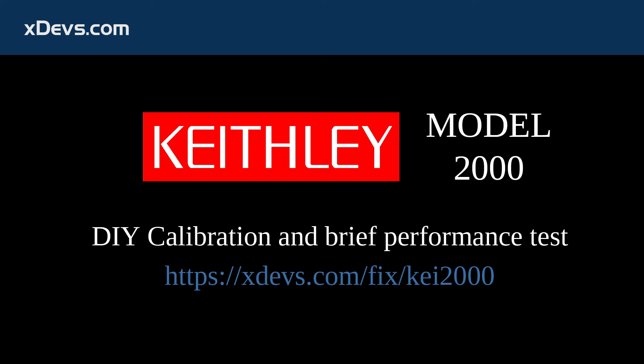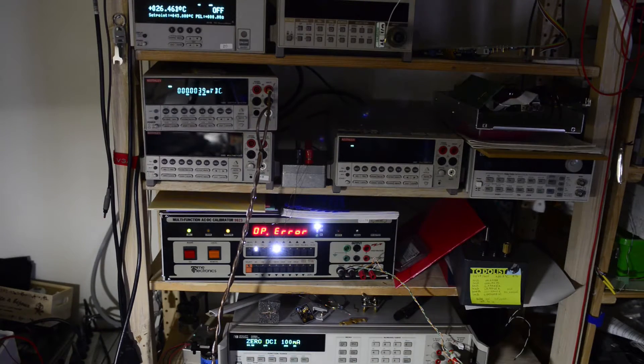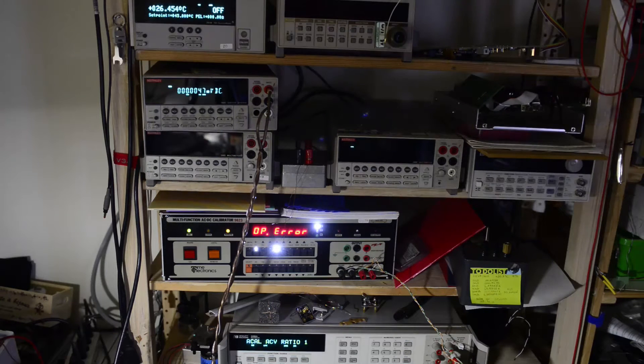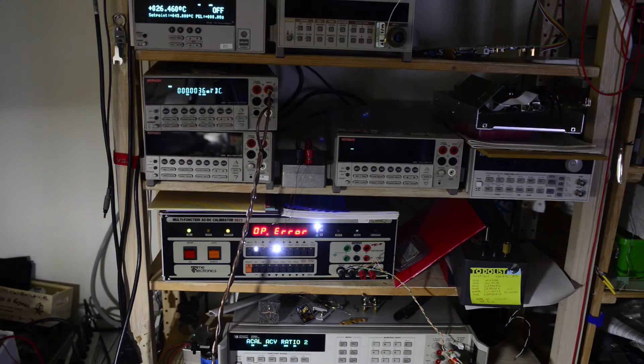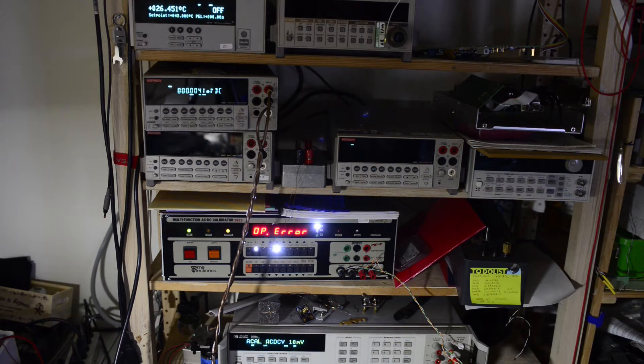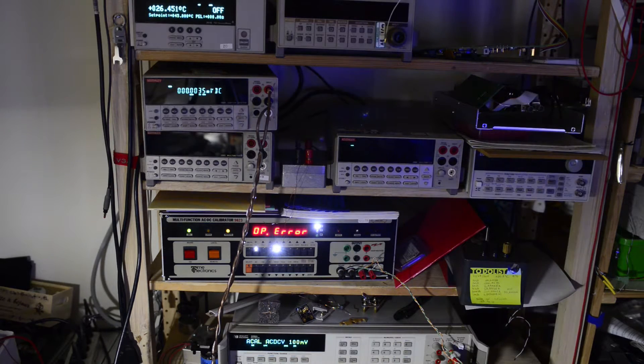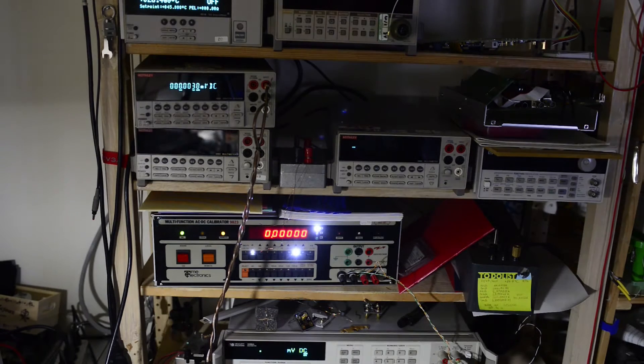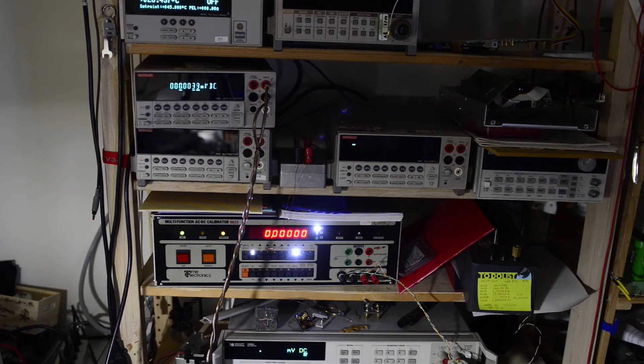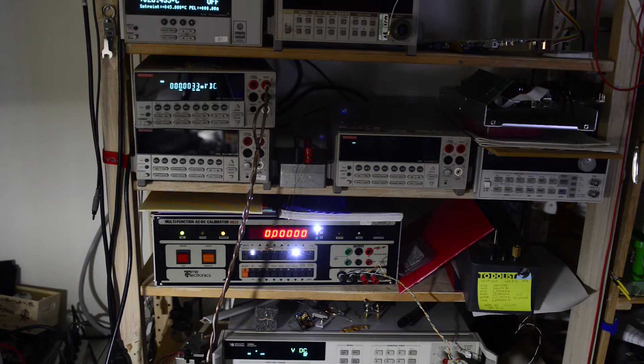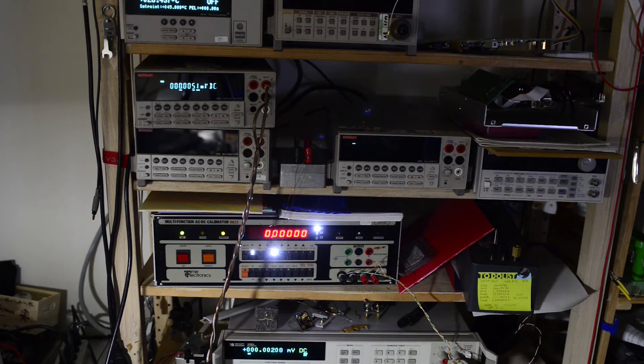In this video I will calibrate and test Keithley model 2000 6.5 digit multimeter. I will use HP3458A reference multimeter and Time Electronics 9823 calibrator. The HP meter finished the calibration procedure already and is ready to use.